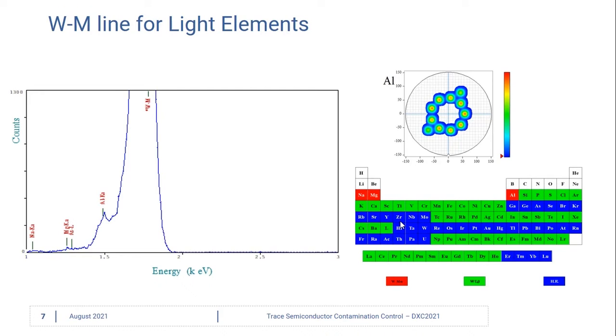Silicon is a large peak and it's always present because it comes from our wafer substrate. In order to get better sensitivity for aluminum and to separate those peaks, we use the tungsten M line to excite the aluminum, but then it does not excite the silicon.